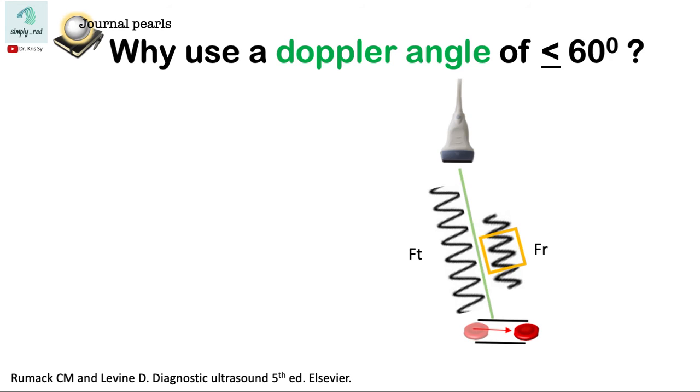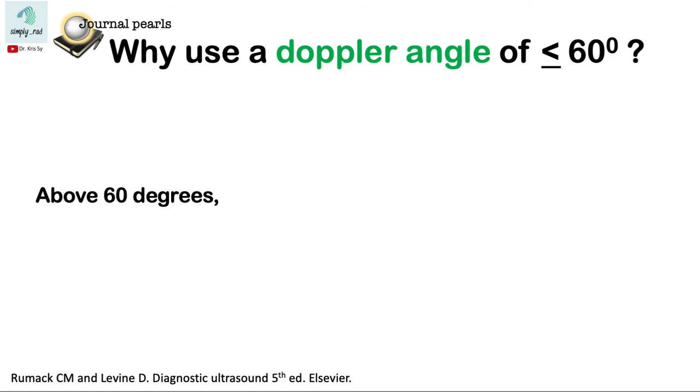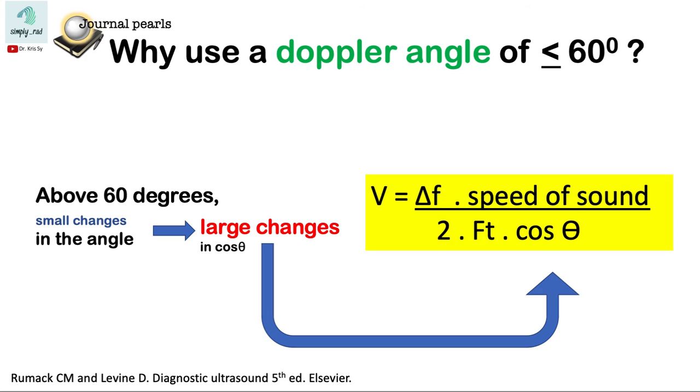So again, why use a Doppler angle of 60 degrees or lower? Because above 60 degrees, small changes in the angle lead to large changes in the value of cosine of the angle, and this would result in a large error in the estimation of the velocity.